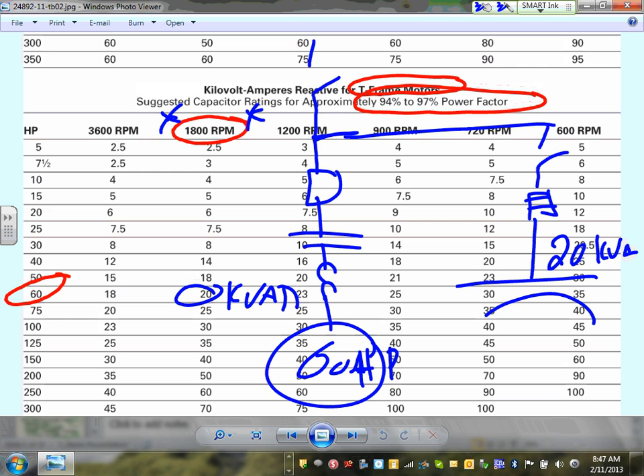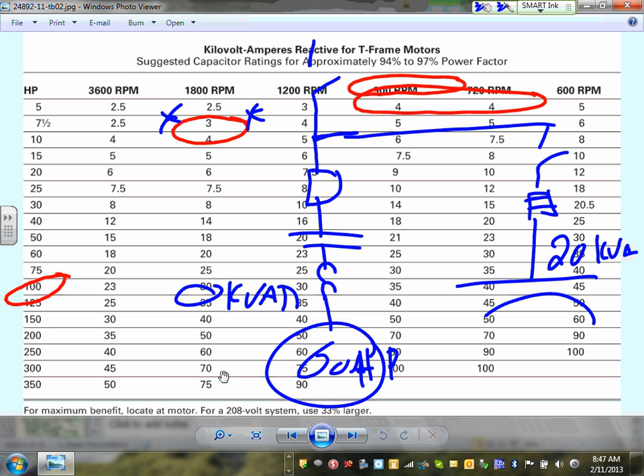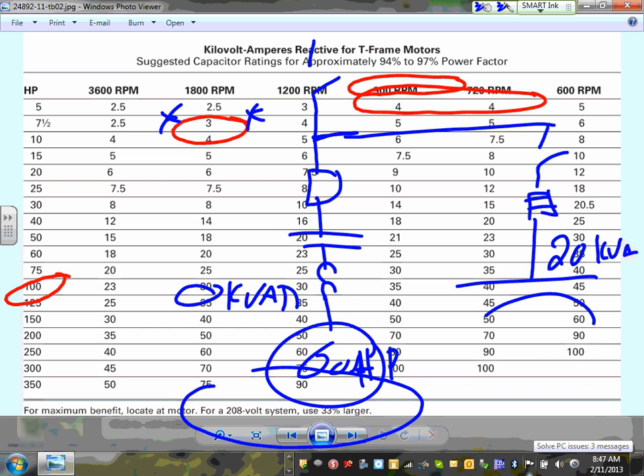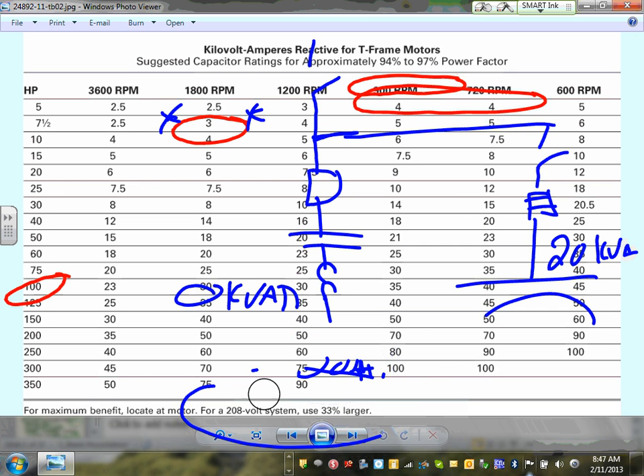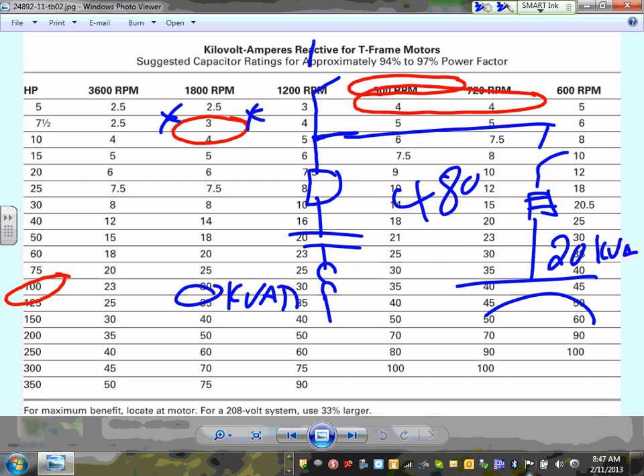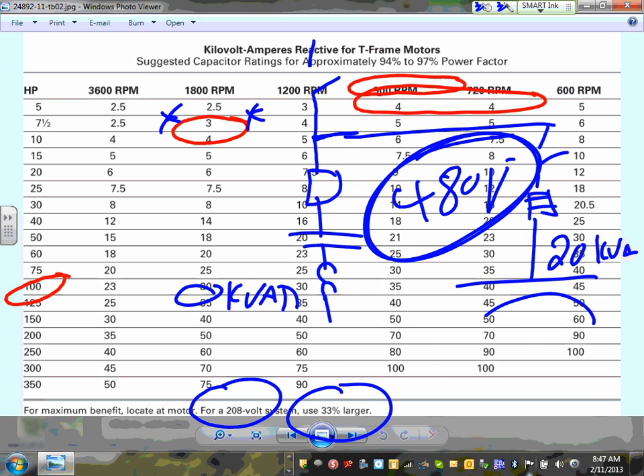Any comments, any questions about this? Straightforward, huh? The last thing I'm going to show you is right at the bottom here. Can you guys see right at the bottom, please? It says, for maximum benefit, locate at motors, for 208 voltage, use, what did it say here? Anybody can read that? This table is for a 480 system, for motors that are running at 480. What if your motor is running at 208? How do you need to adjust it, Jeff? You take the numbers that you got here and up them 33%.